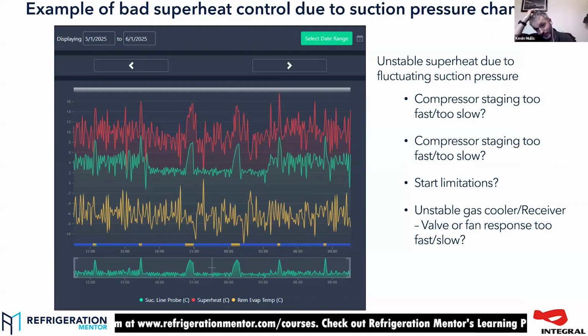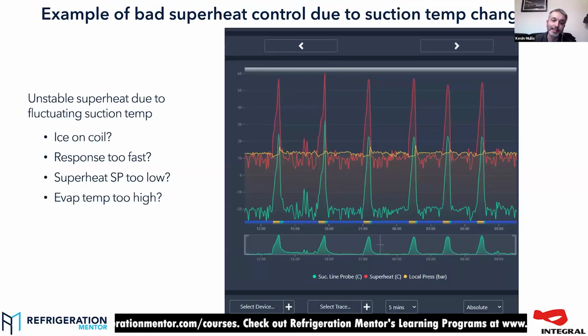So, just on the other two points I had on there: is a superheat set point too low? Is the evaporator temperature too high? And the reason I say superheat set point too low, we talked about it with Danfoss, there's a minimum stable point for every evaporator. If you try and set the superheat below that, the coil is by design inherently unstable below that point, and you will never ever stabilize the outlet.